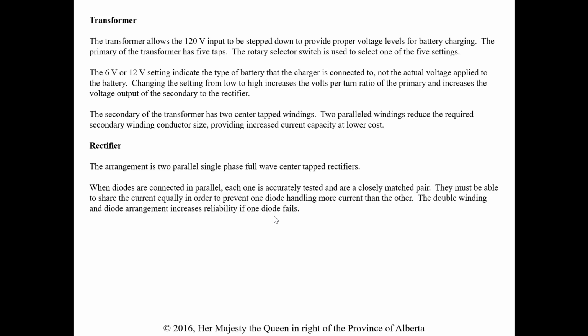The 6 volt and 12 volt settings indicate the type of battery the charger is connected to, not the actual voltage applied to the battery. Changing the setting from low to high increases the volts per turn ratio of the primary and increases the voltage output of the secondary to the rectifier.